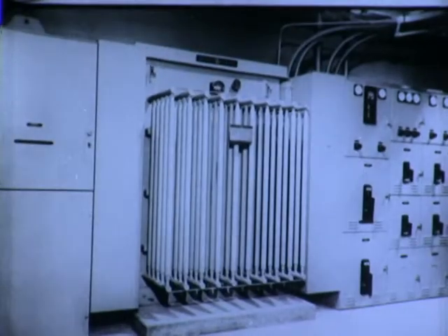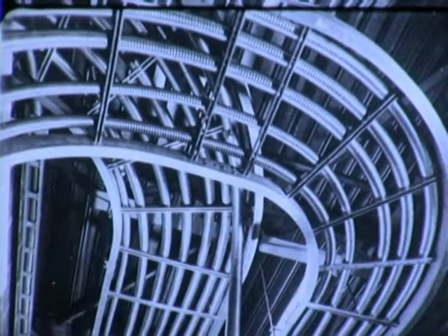The new rollout equipment is in no way intended to be competitive with metal-clad. Rather, it can broaden your potential market to include those applications where your customers cannot justify metal-clad switchgear. Available in 2400 volts to 13.8 kV ratings, our new rollout switch and fuse equipment is applicable to light-duty circuits usually found in commercial and small industrial systems. Typical examples include switching and protection of load center transformers, small power transformer banks, lighting transformers, and light-duty general-purpose feeder circuits.